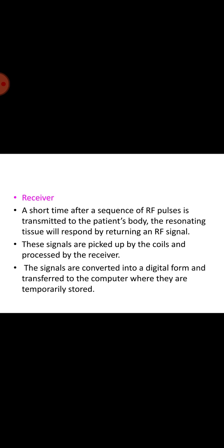And the next topic is the receiver. A short time after a sequence of RF pulses is transmitted to the patient's body, the resonating tissue will respond by returning an RF signal. These signals are picked up by the coils and processed by the receiver. The signals are converted into digital form and transferred to the computer, where they are temporarily stored.